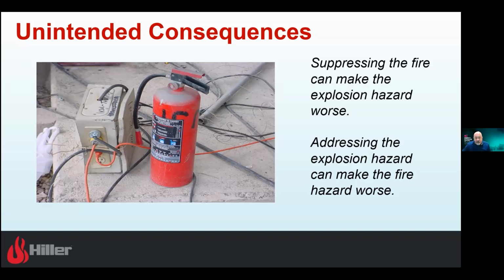Of course, the third option is actually run a test, see whether it explodes or see whether it burns, and then use that data—obviously the real world trumps theoretical every time. So we're starting to see a lot of people engage with these large-scale fire tests. I think that's where the industry is going. It doesn't necessarily fit within the 9540A framework, which is obviously the basis we utilize in order to design these systems. We start with that fire test. We do tend to be a little conservative, looking at gas levels on a cell level.